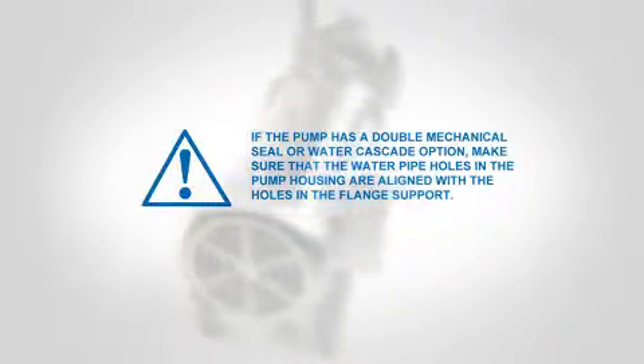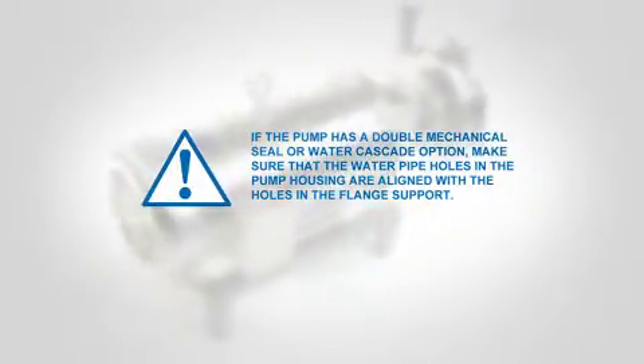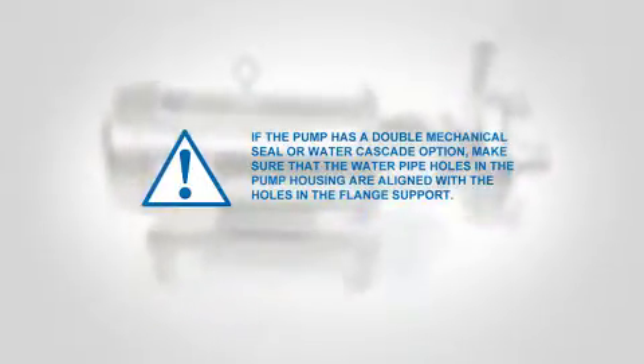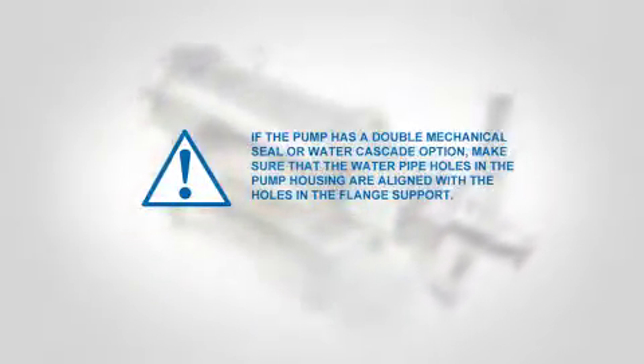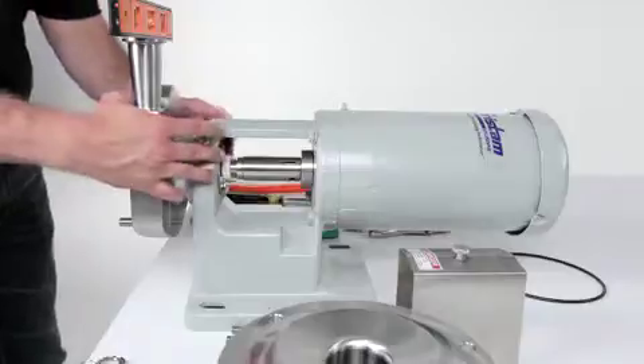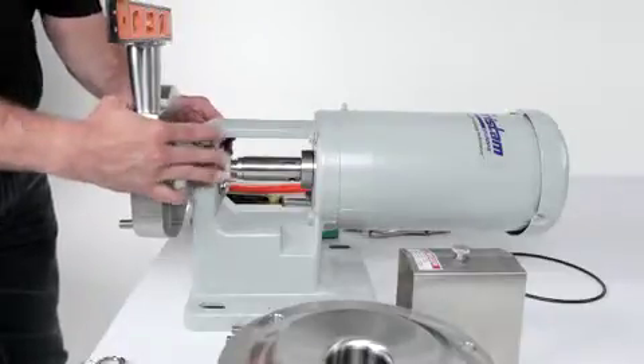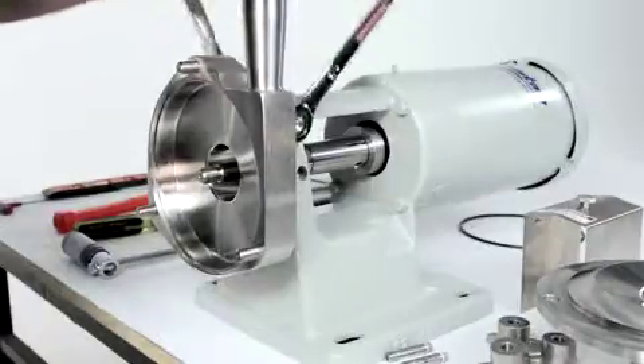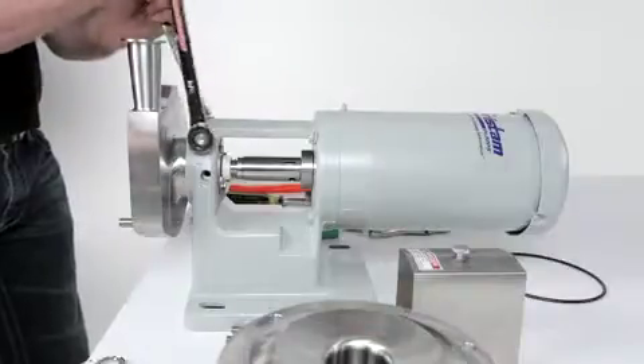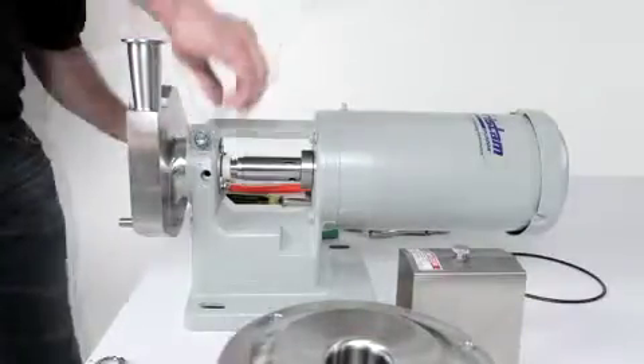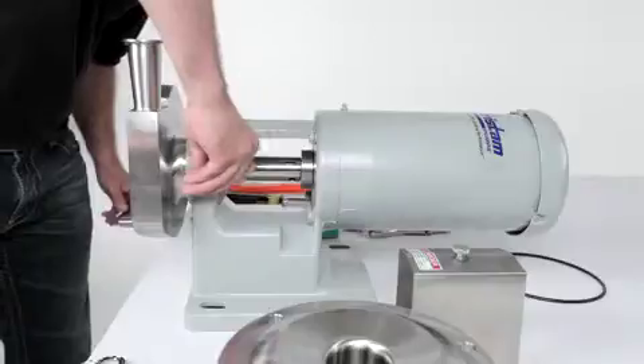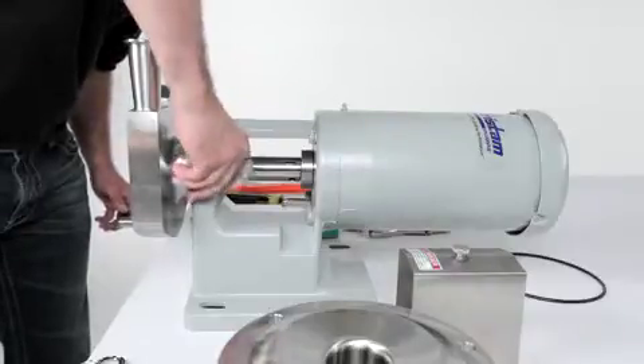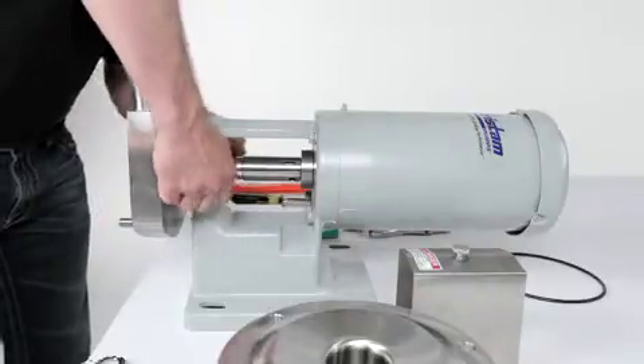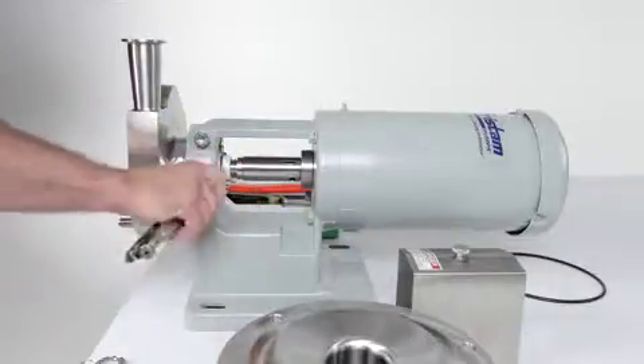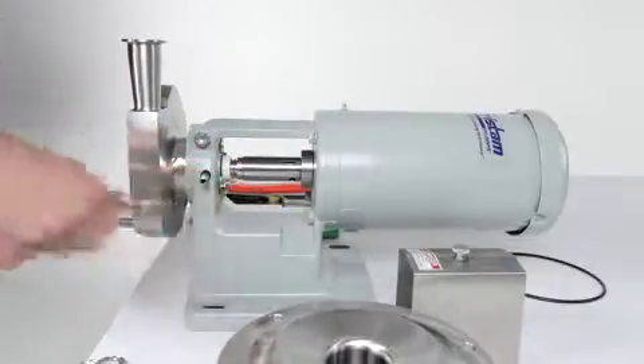If the pump has a double seal, make sure that the water pipe holes in the pump housing are aligned with the holes in the flange support and that the pump head is level. While holding the pump housing against the flange support, tighten the clamping bolt in the flange support. Install the seal water pipes for double mechanical seals or water cascade option by threading them into the housing and tighten. You are now ready to install the rotating seal assembly.